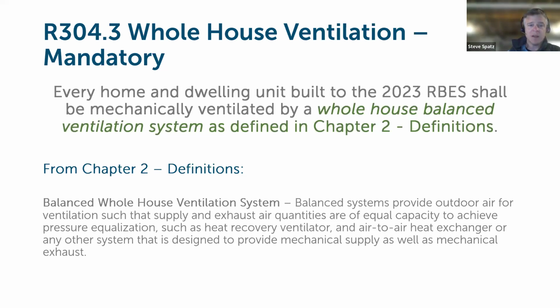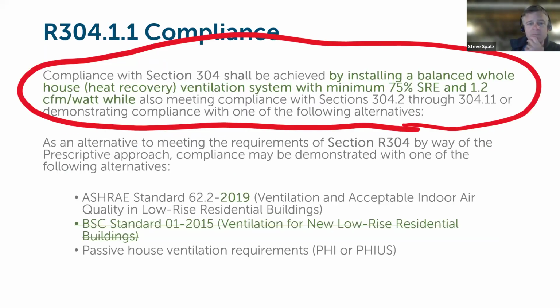Defining that we need to have balanced heat recovery ventilation is mandatory moving forward for the 2023 RBES. When we're doing this, you're actually designing the piece of equipment to do the ventilation for the building in a similar methodology as you would be for designing and sizing a heating or cooling system for the house. You're taking the specific details of the size of the building, the location of the building, what climate zone it's in, number of occupants, air leakage through the building shell, and those data points go into calculating the ventilation requirements, how many CFM of air exchange is necessary to maintain good indoor air quality, and in our climate really keep relative humidity in check with that system.